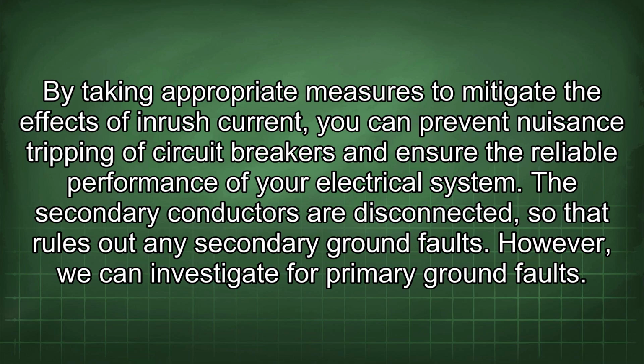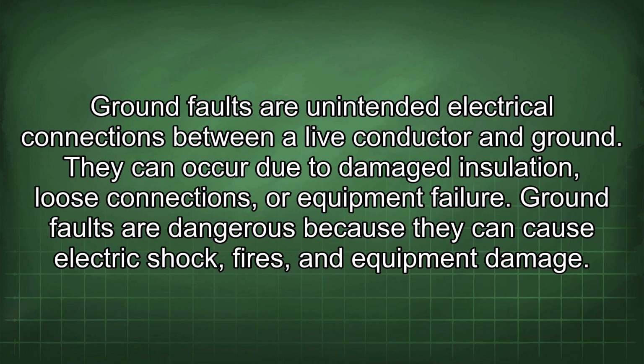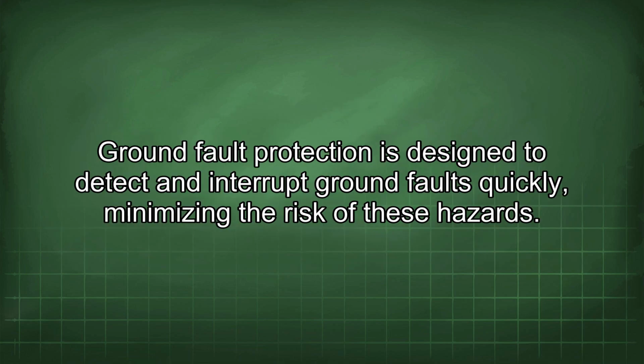The secondary conductors are disconnected, so that rules out any secondary ground faults. However, we can investigate for primary ground faults. Ground faults are unintended electrical connections between a live conductor and ground. They can occur due to damaged insulation, loose connections, or equipment failure. Ground faults are dangerous because they can cause electric shock, fires, and equipment damage. Ground fault protection is designed to detect and interrupt ground faults quickly, minimizing the risk of these hazards.